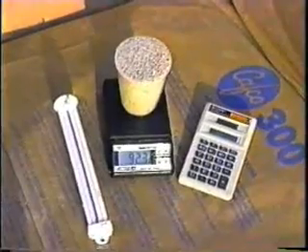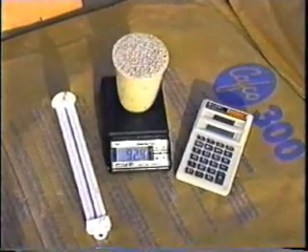The proper amount of water and mix are crucial to the successful installation of wet mix materials. Therefore, the mixing area should be equipped with both a scale and water metering device to ensure that a constant water quantity per mix and water to product ratio are maintained. Mixer and nozzle density should be checked periodically to ensure that the optimum performance of the material is being achieved.